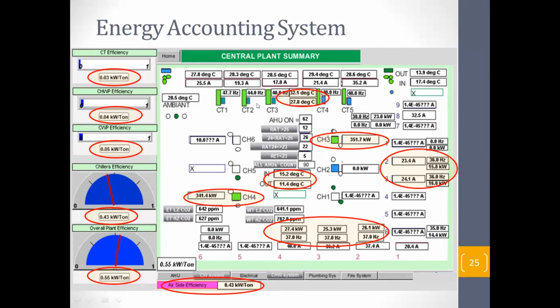2 chillers. See how many cooling towers are running. All 5 cooling towers are running at low speed. So this is not our normal practice. Normally, with 2 chillers, we run 2 cooling towers, 2 condenser water pumps, 2 chilled water pumps. And they're running 2 chillers with 5 cooling towers and 3 condenser water pumps at a much lower speed.